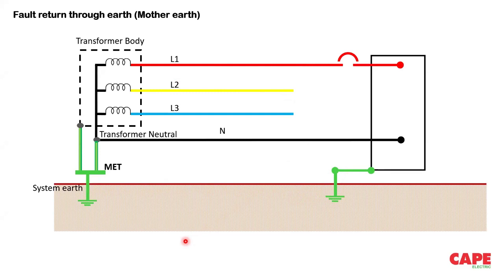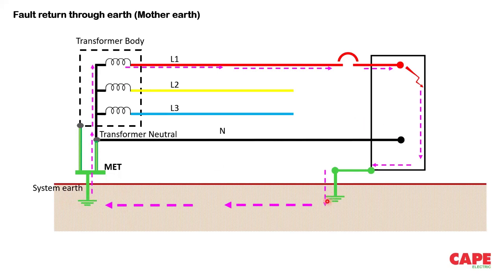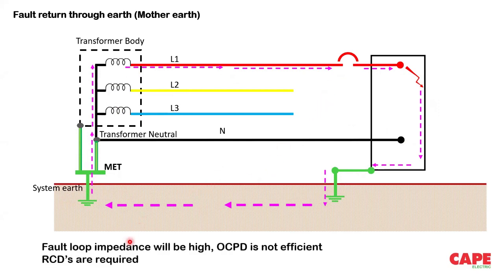The technique explained in the previous slide, fault loop impedance and disconnection by an OCPD, technically will not work in this particular case. For disconnection, what we require is a different technique. In this case, the fault current flows through the earth electrode, through the soil, through the earth electrode of the source, and returns. The problem here is that the fault loop impedance will be very high, of the order of a few ohms. Say, for example, 1 ohm, 2 ohm, 3 ohm, not actually, it's always more than 2 ohm, maybe 10 ohm, 15 ohm, like that. An OCPD is not at all efficient in this case, and you always require a device called an RCD, residual current device.